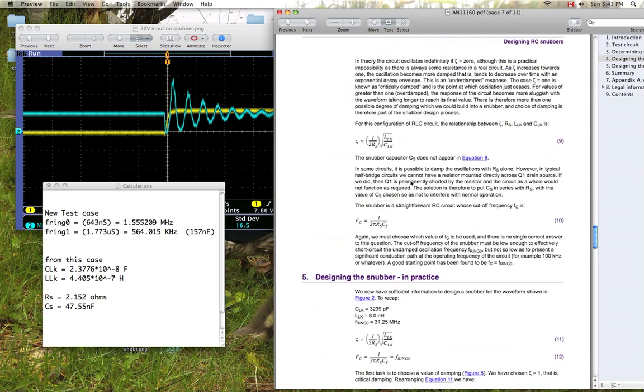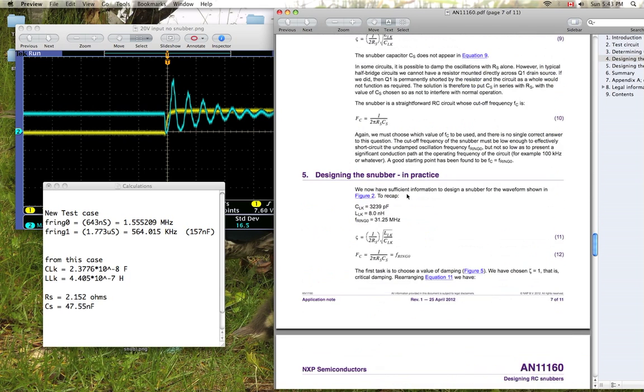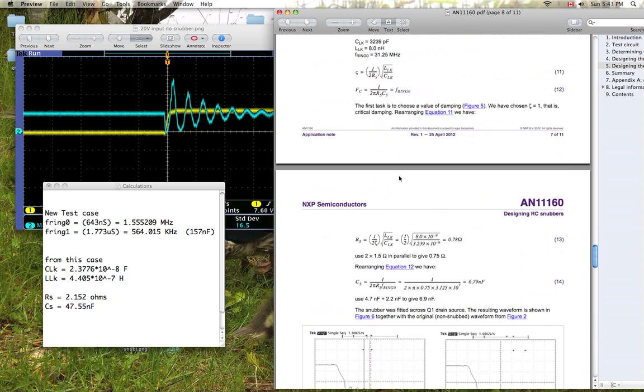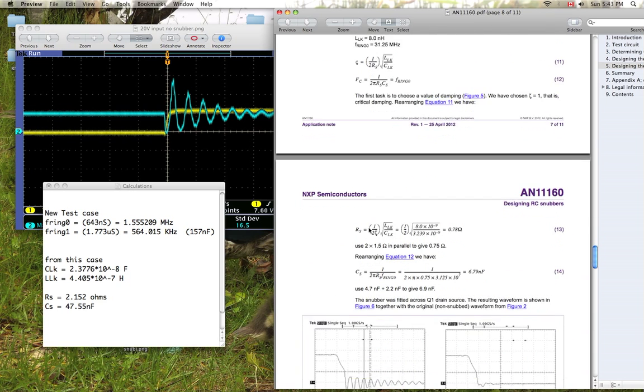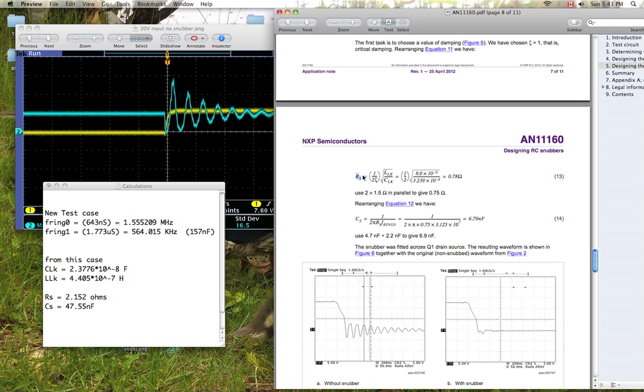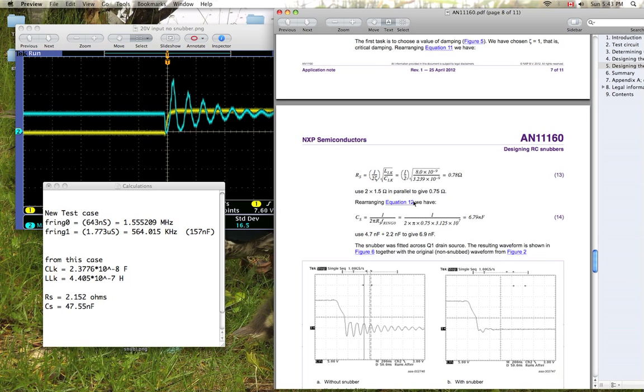And once again, you can just go through your calculations here. You can solve for the snubbing resistance here. Let's see if I can find the equation. That's buried in here somewhere. Oh, here we are. So you plug in this here with your inductance and your capacitance and your damping ratio to get your optimum snubber resistance for that damping ratio or factor. So from that you get your optimum snubber resistance.